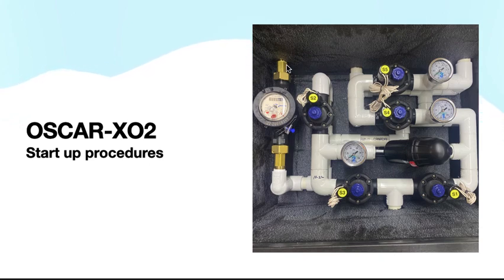The connections you'll make is on the other side of this flow meter. This is your supply line going out to your Oscar drain field. Here is the flush line coming back from your Oscar drain field. So these 2 lines on either side over here are the ones going out to the Oscar. This one in the middle, on a lower elevation than these other 2, this is that vent line going all the way back to the beginning of the system. And in here is the line coming straight from the pump through the riser and then into the headworks. So it's those 4, from the pump, out to the Oscar, from the Oscar, and the vent line going back.